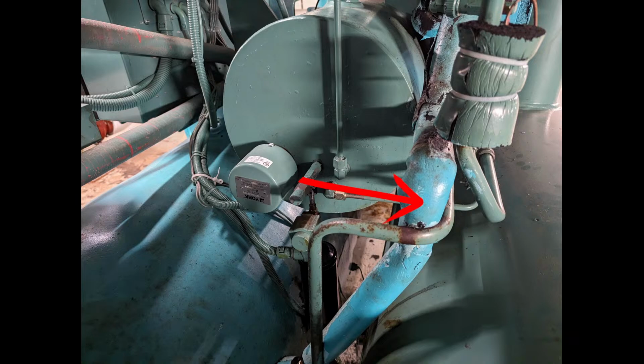The size of the machine does have an impact here; this would be a smaller one. Some larger units have a different design, where the tank or sump is down underneath the condenser, and the piping for the eductor assembly runs down there, changing the exact location of the solenoid along with the filter. But generally, this line is the hot gas line coming off the top of the condenser feeding into the eductor assembly. There's an eductor block inside here. Some other models have a slightly different eductor assembly, so it varies a bit, but the overall core basics of how York does this stays relatively similar.